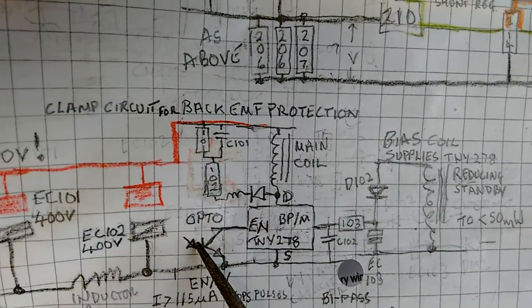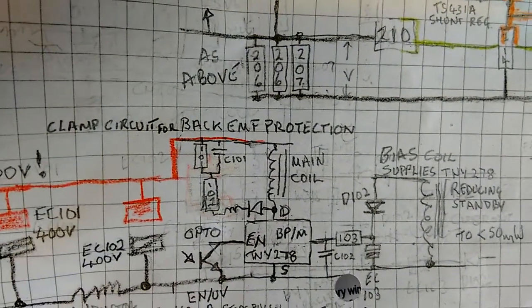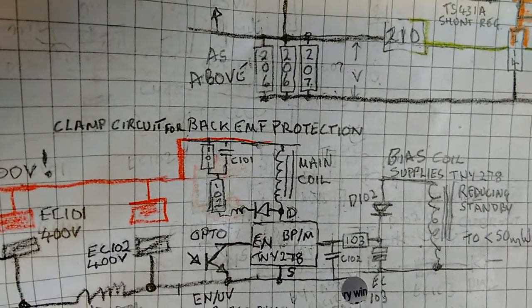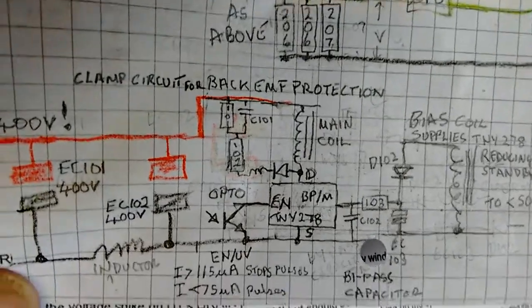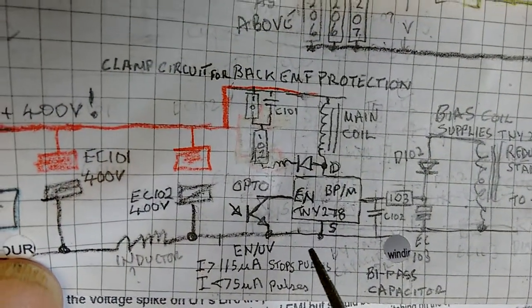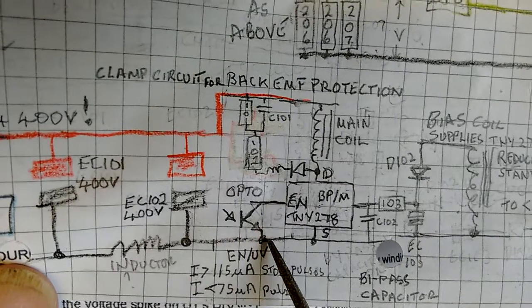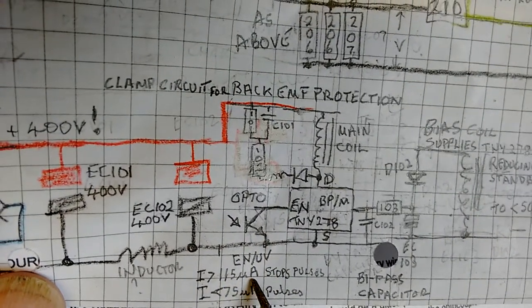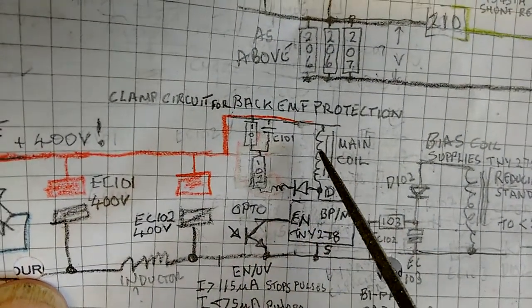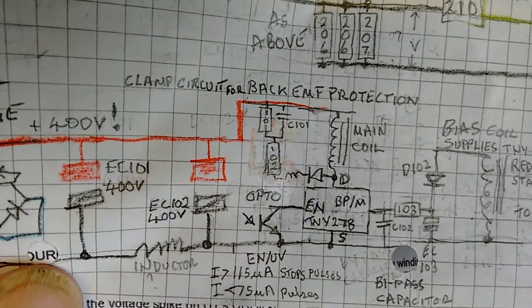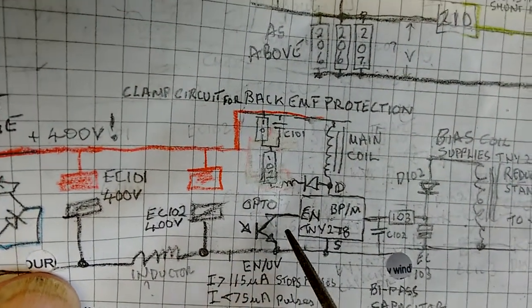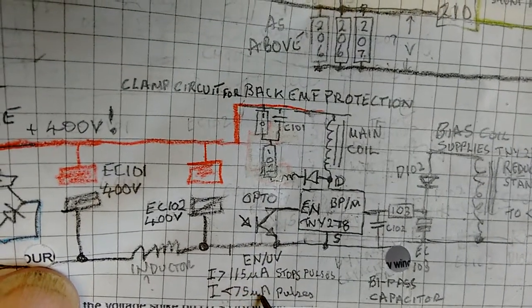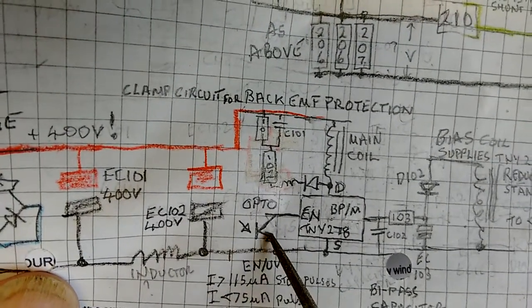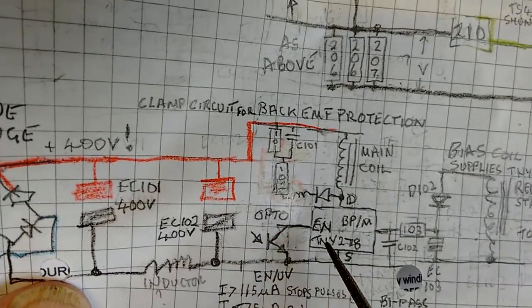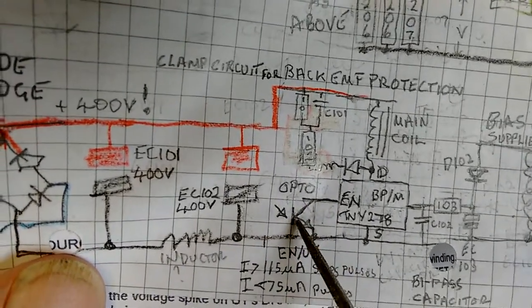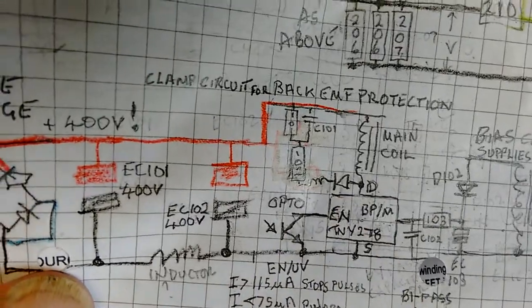So if this is switched on, then a current flows, and if it's greater than 115 microamps, this stops switching the transformer on and off until this current goes back down again to less than 75 microamps. So it's going to pulse if this isn't on. If it isn't on, it pulses. If it is on, it doesn't pulse.